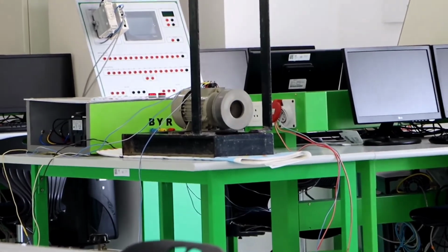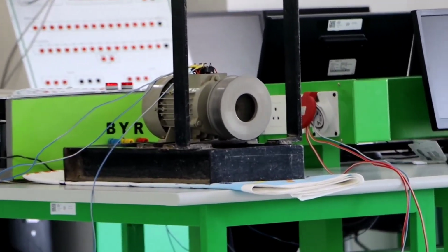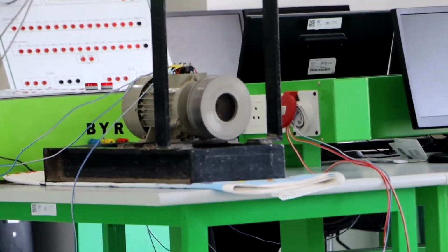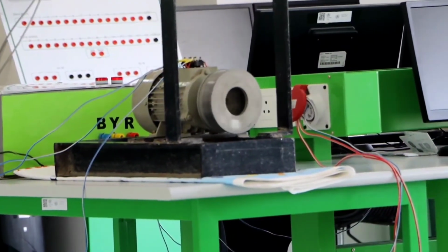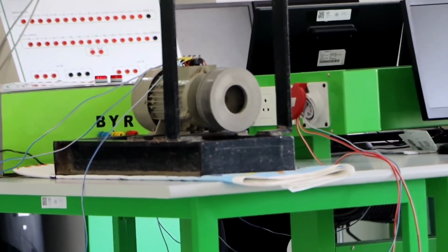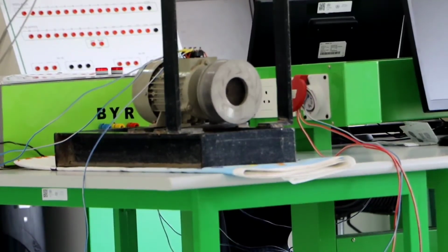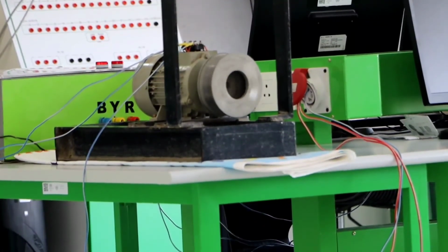So I have given it. You can see there the motor is first running in the forward direction. The time delay given was 10 seconds. Now I have changed it to the reverse connection. Here, I have given control, and the motor is trying to run in the reverse direction. This process is cumulative and this operation is automatic. There is no human interference in it. Just give on-off control from my system and I can see that automation is achieved.